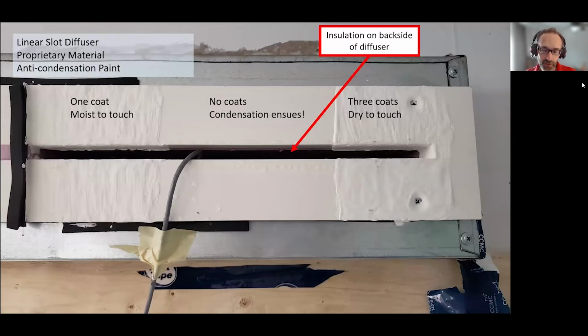One particularly interesting thing we tried - I mentioned this anti-condensation paint that a colleague got me onto. We took one of these proprietary diffusers and set it up with three different situations. In the middle, no anti-condensation paint. On the left, one coat, and on the right, three coats, which is the manufacturer-recommended amount. I didn't take actual thickness measurements - didn't have a thickness gauge with me at the time, so I don't know exactly how thick I got it.